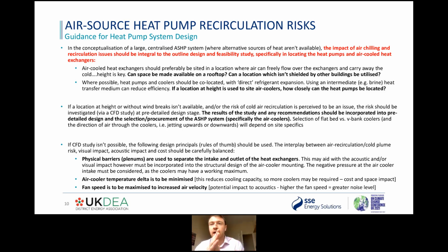If a location at height is used to site these air coolers, if you're placing the evaporators on a rooftop, how closely can the heat pumps be located? What we've seen is that if you have a large separation distance between the heat pumps and the air coolers, it means you sometimes have to introduce a brine loop, which can impact your COP.